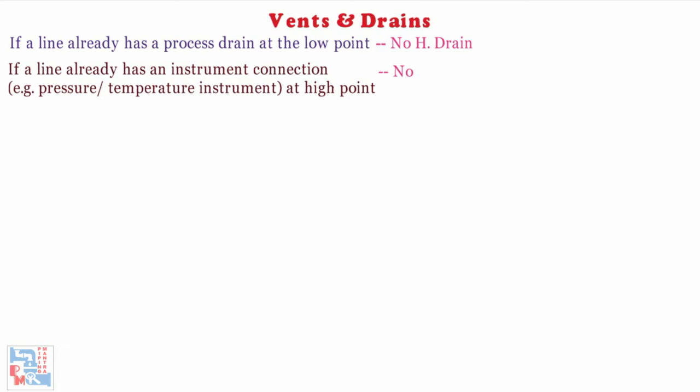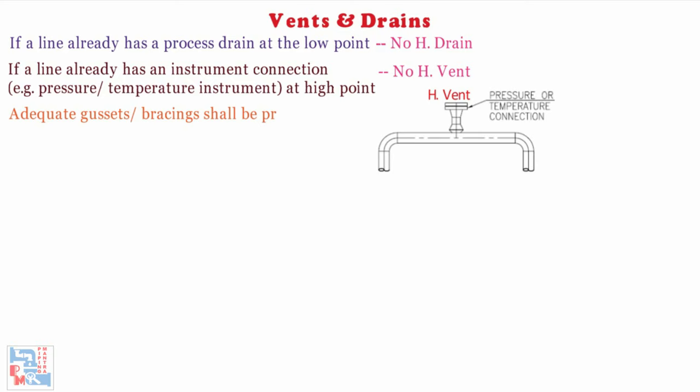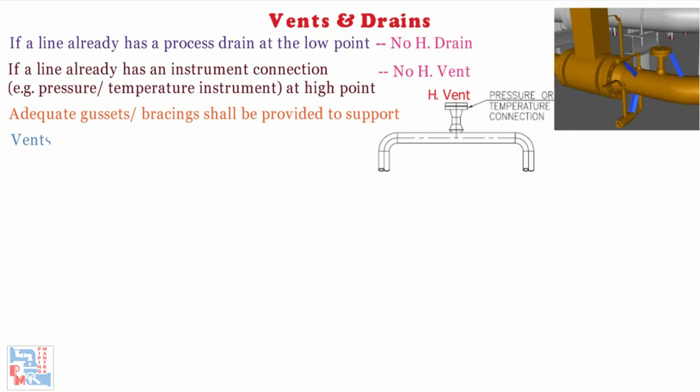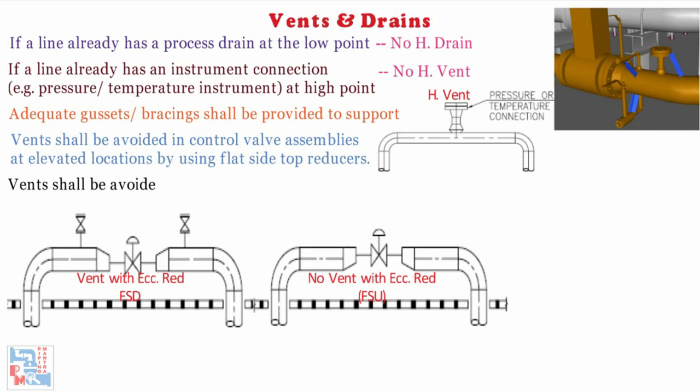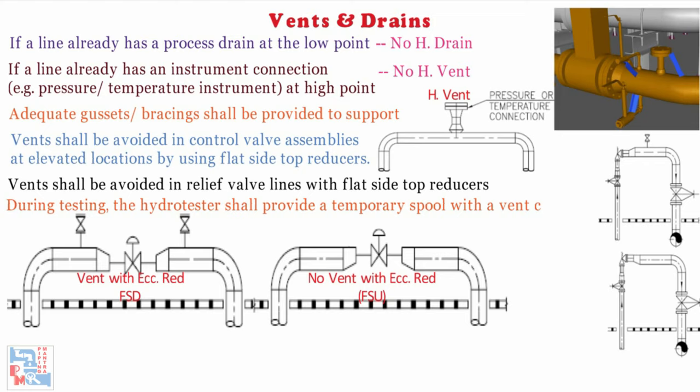Adequate gussets or bracings shall be provided to support the vents and drains in case of lines subjected to vibrations. Vents shall be avoided in control valve assemblies at elevated locations by using flat-side-up reducers. The same is applicable for outlet of relief valve lines; flat-side-up reducers shall not provide a high point vent, as during testing the hydrotester shall provide a temporary spool with the vent connection in lieu of the control valve.